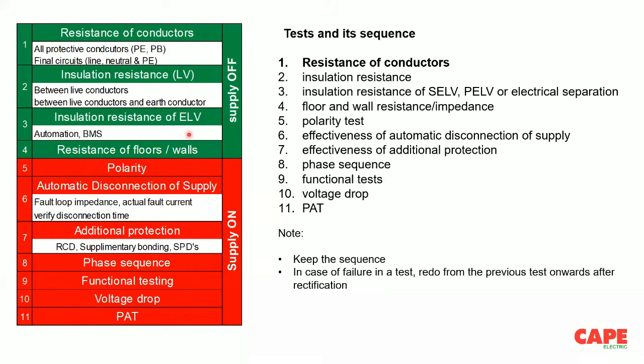When it comes to testing, there are 10 tests included in the standard, whereas in my slide, I have put 11 tests. The 11th one is actually PAT, the portable appliance test. Probably it may come into the standard at a later stage. So I will explain the first one, resistance of conductors. In the next two slides, I explain the first inspection point and the first testing point, so that you can ascertain the situation of electrical safety in your building.